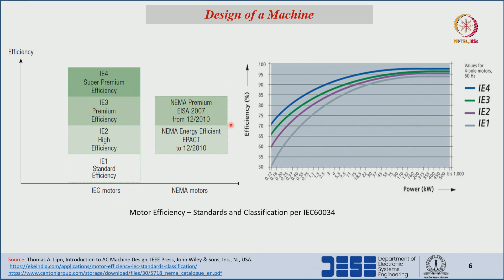For NEMA standards there are two classes: NEMA Premium EISA 2007 and NEMA Energy Efficient EPAct. From the image, we can observe that for a 3 kilowatt rating: an IE1 machine has about 80% efficiency; IE2 has about 85%; IE3 has 85–90%; and IE4 has greater than 90% efficiency. The figure shows how efficiency varies with different power levels across different standards.